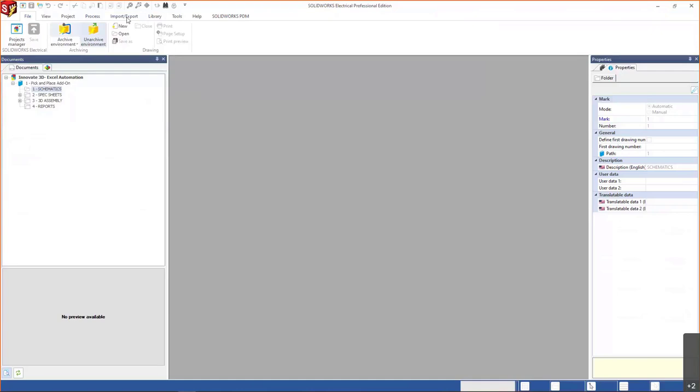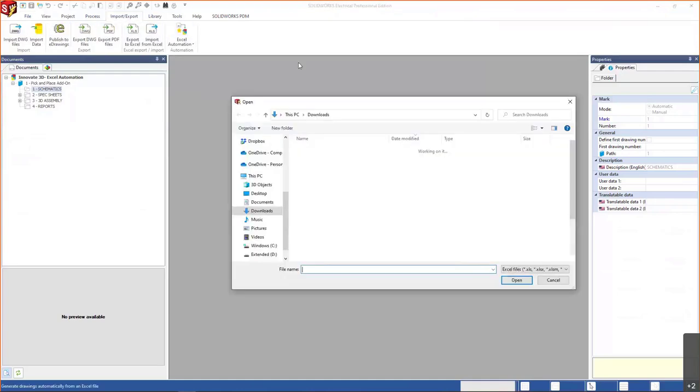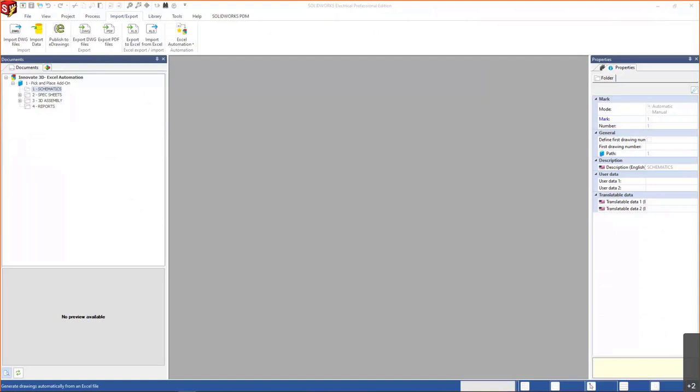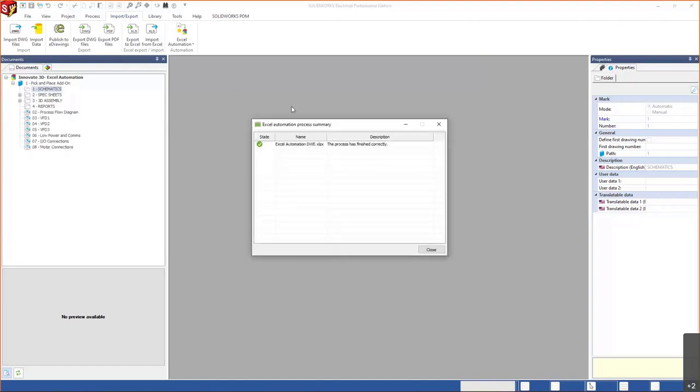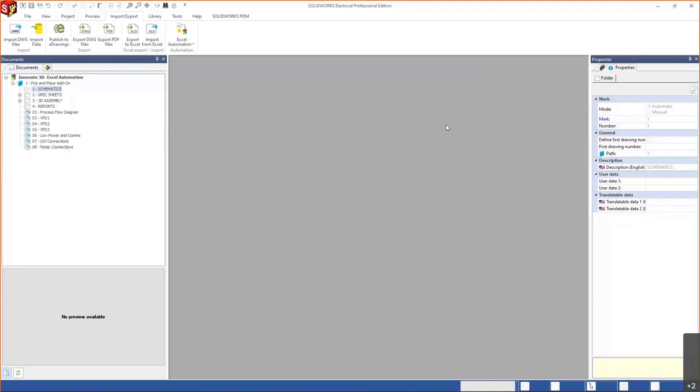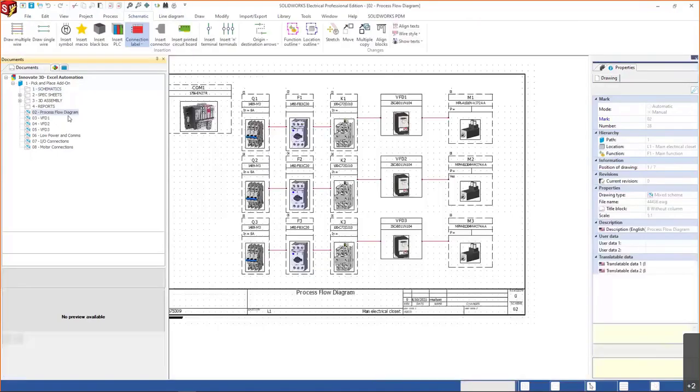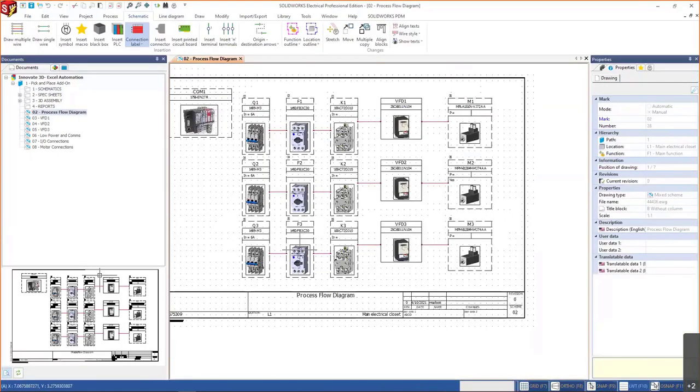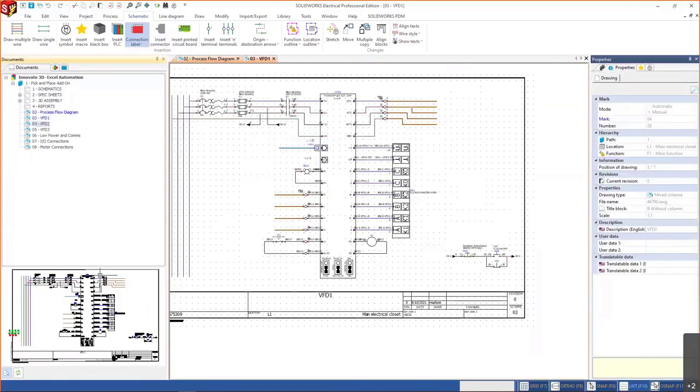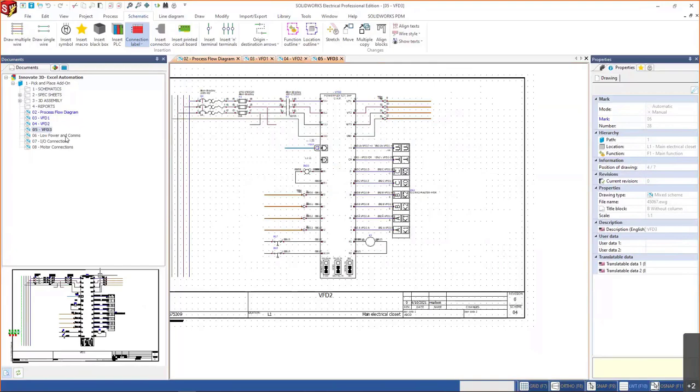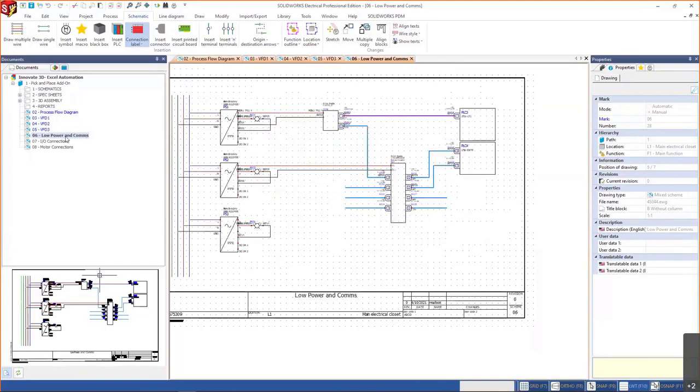And I can save this document. And then when I go to – into my project, I can take my project and point it to that Excel sheet. And then SolidWorks Electrical will then read that Excel sheet and produce all those macros where they need to be based on my inputs. So, I said I needed a three-motor system. Okay, so it's going to draw me three motor lines. Well, those three motor lines are going to need, in this case, three VFDs. So, I've got some VFD schematics.